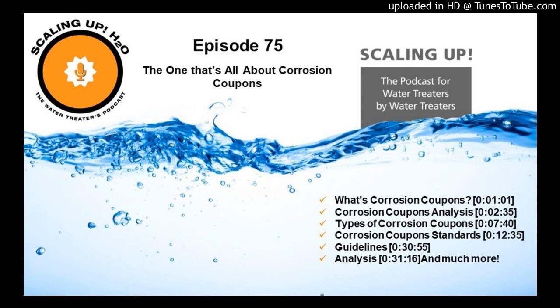I set them all out flat on our bench, and then we use the envelopes that you gave us to identify the serial number to the coupon, and then we start weighing each coupon again down to the 10,000th of a gram. That's very, very specific. And of course, that's not your ordinary scale. These are special metallurgical scales. And then once that's done, we take a final picture of what that coupon looks like front and back after it's cleaned. And then we start doing math. We do the equation to figure out how many mils per year was lost during that exposure time. And again, mils per year is 1,000ths of 1 inch.